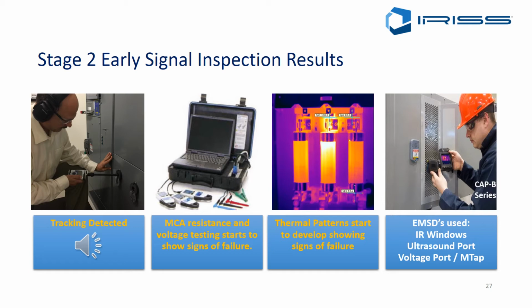Also, at this stage, motor current analysis, or the voltage and current testing, is going to start to show the early signs of failure, and we're going to start to see thermal patterns develop around the failure points. So there we have a visual verification and audible verification of this fault developing, and all the time we're using EMSDs and the panels are in a safe, closed and guarded condition, and it's very quick and easy to do.